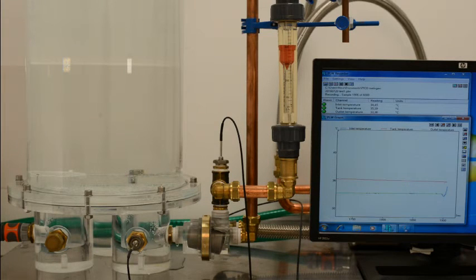Now you see the temperature increasing, the inlet, the blue line now overtaking the red line, which means that the valve should now start to switch. So you look at the valve now, it has fully switched. So in a few seconds of switching time, the valve is now completely moved to the open position. So now the flow is directed via the tank, which you can see because the outlet temperature, the green line, is now starting to follow the red line, whereas the inlet temperature is much higher.